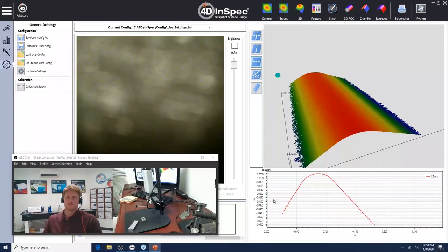Can it measure a chamfer that has rounded corners? And related or expanding on that, we have a chamfer on a gear flank. Gear flanks are non-planar, still capable? So the short answer to both is yes. We have actually measured chamfer angles on hypoid gears and on standard gears, and that's not been an issue.